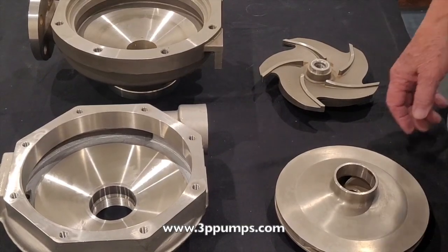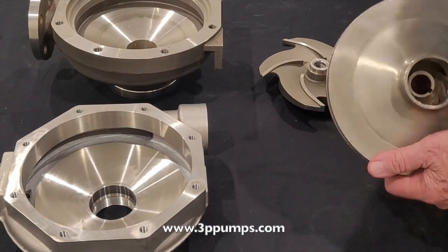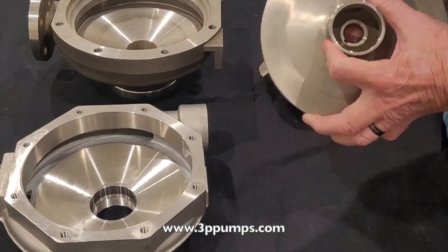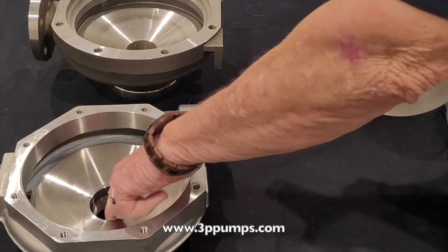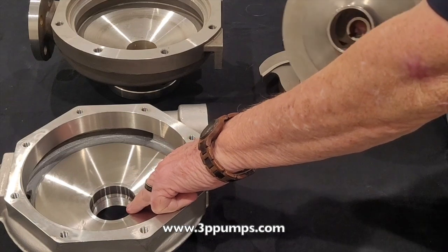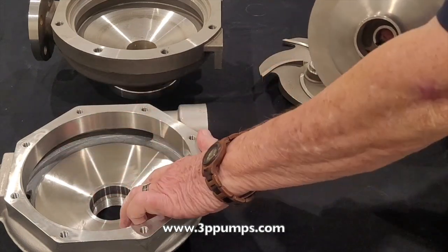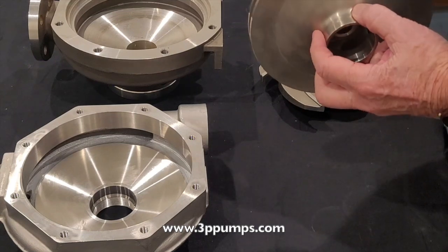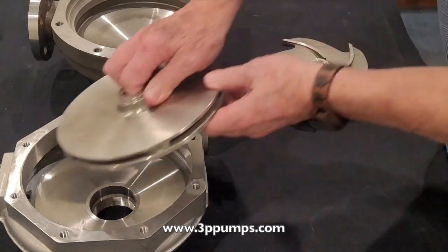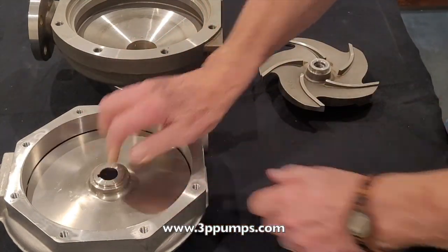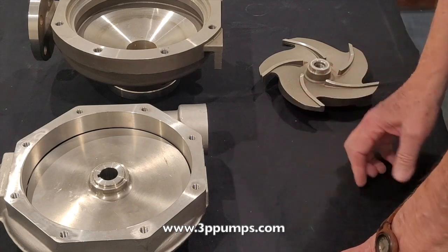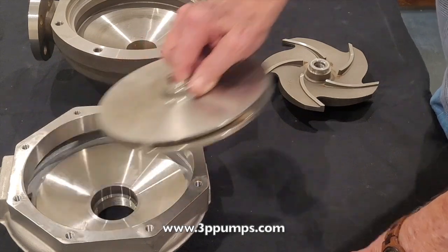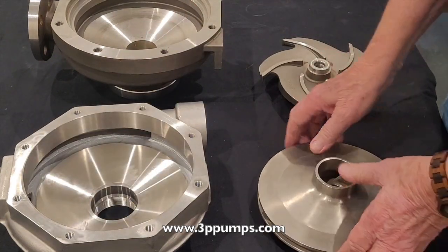Okay, to further explain the impeller situation here, this is a closed impeller, and where it seals or keeps the liquid from going back to suction is right in this area right there. That's a close tolerance bushing, basically, is what it amounts to. So this right here has to be close tolerance to this in here for this impeller to be the most efficient. The closer it is, the better your efficiency of your pump. And that's one of your biggest determining factors on efficiency of the pump.